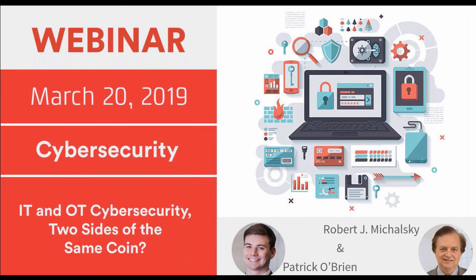So in the latest version of IEC 61511, which is really focused on end users, the operators of industrial facilities, there are two key requirements that have been added for cybersecurity. The first one is that cybersecurity risk assessments are now required as part of the assessment phase. So not only do you have to do the process hazard and risk assessment, you also have to do a cybersecurity risk assessment to understand what the vulnerabilities are and how that could potentially influence the safety system. And completing that is now a mandatory part of the standard.